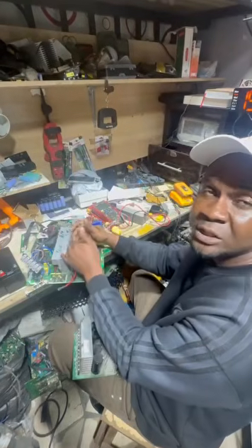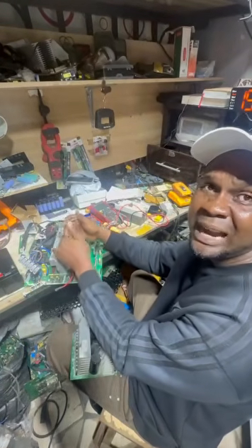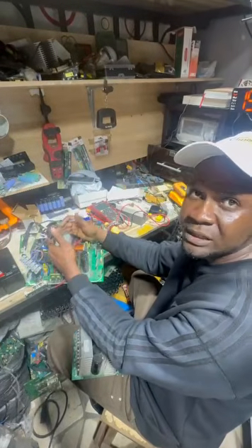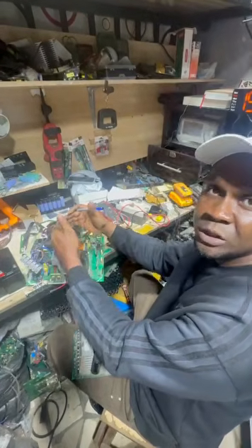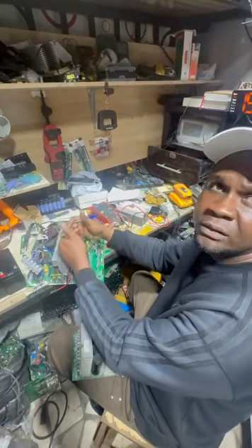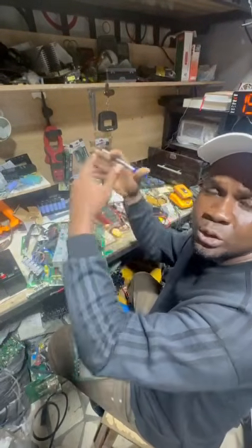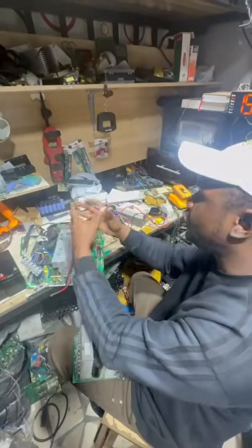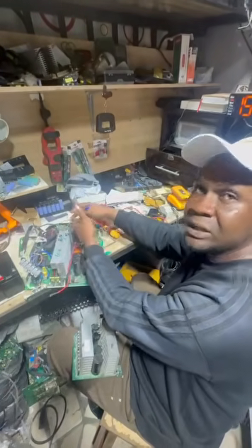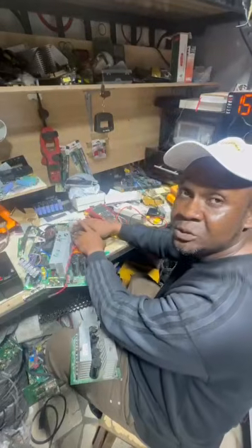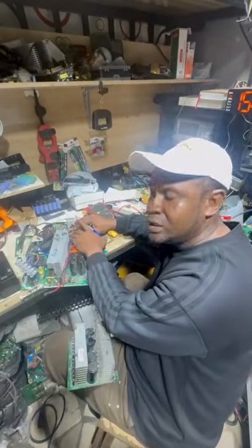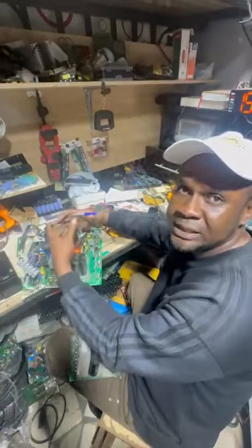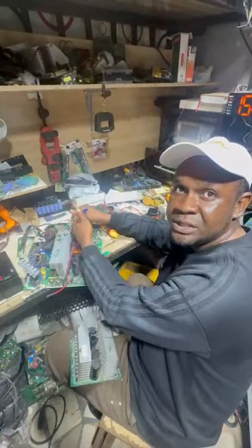The output of this is going to be an AC of a very high frequency, which cannot be used. So what will happen is to convert that AC output voltage back to DC. The DC that will be generated at that point will be stored in the reserve section where you have the capacitor. The capacitor here is rated around 400 volts to have the storage capability for the voltage that will be converted from AC back to DC.